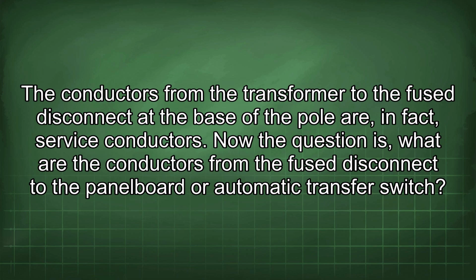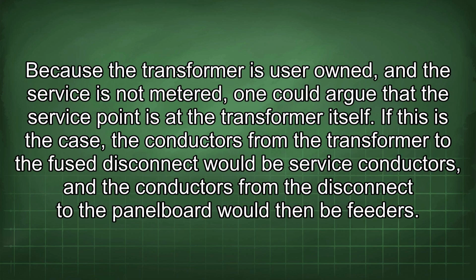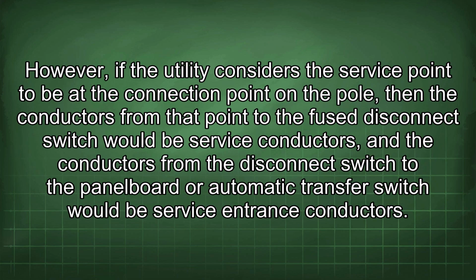Because the transformer is user-owned and the service is not metered, one could argue that the service point is at the transformer itself. If this is the case, the conductors from the transformer to the fused disconnect would be service conductors, and the conductors from the disconnect to the panel board would then be feeders. However, if the utility considers the service point to be at the connection point on the pole, then the conductors from that point to the fused disconnect switch would be service conductors, and the conductors from the disconnect switch to the panel board or automatic transfer switch would be service entrance conductors.